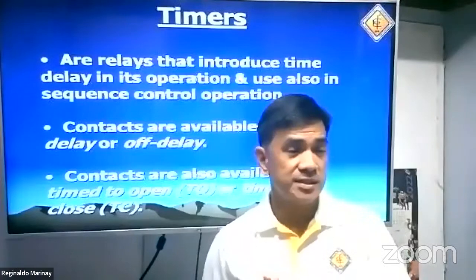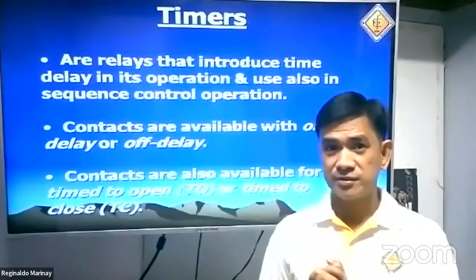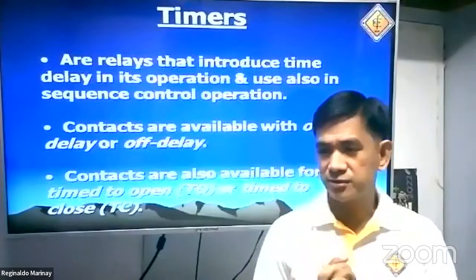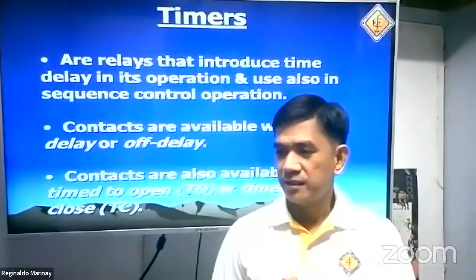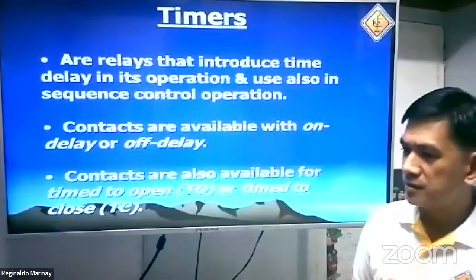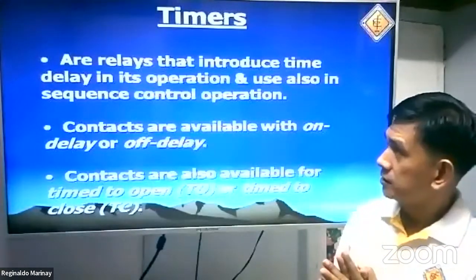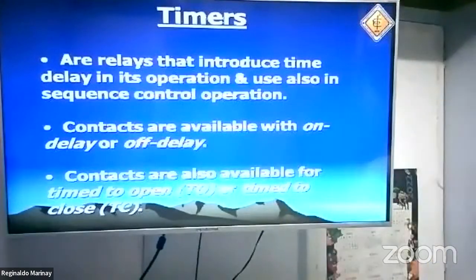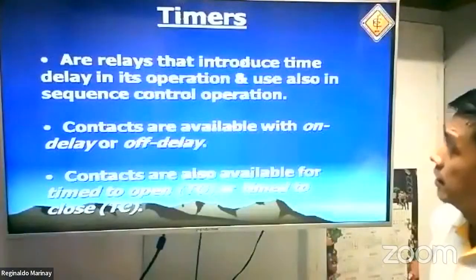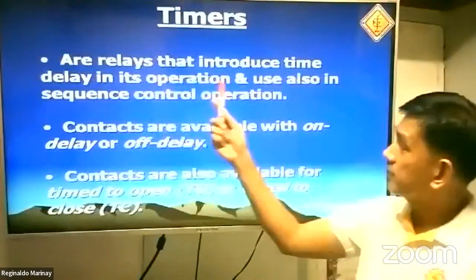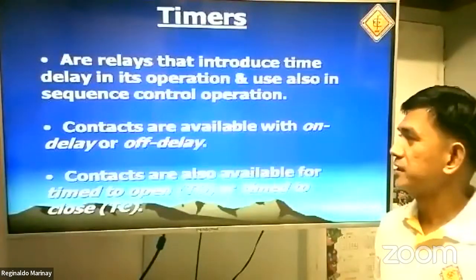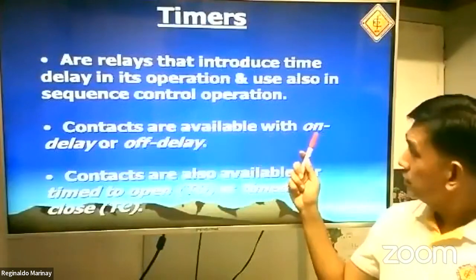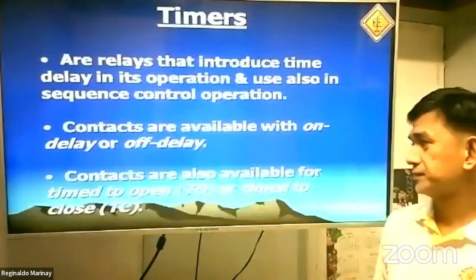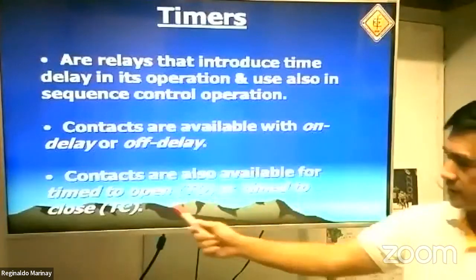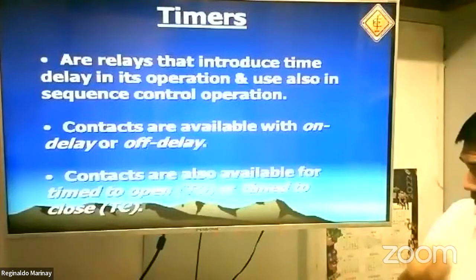Okay, let us continue our discussion about industrial motor control. This is actually part 2 of our lecture on industrial motor control. We have the topic, the timers. So what are timers? These are actually timing relays. Timers or timing relays are relays that introduce time delay in their operation and are also used in sequence control operation. The contacts are available with on delay or off delay. The contacts are also available for time to open or time to close.